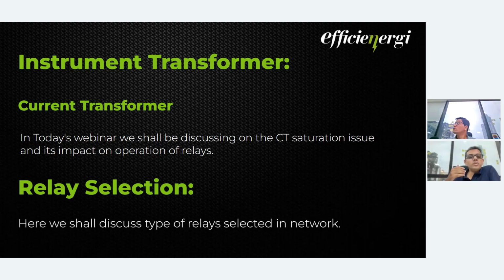These current transformers will play a very outsized role when it comes to ensuring that relays are behaving the way they are supposed to. Relays are tripping at the time and the magnitude at which they are supposed to trip. So what does happen when that CT doesn't operate in the zone that it is supposed to operate? What does happen when a CT gets saturated? That's one of the key areas which is ignored when it comes to functioning of these relays.